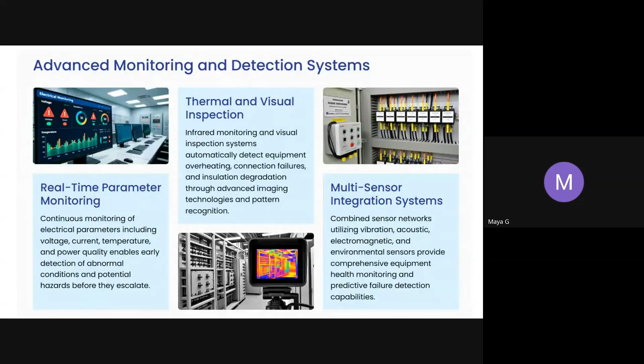So, advanced monitoring and detection systems, I have mentioned a few. Real-time parameter monitoring: continuous monitoring of electrical parameters, including voltage, current, temperature, and power quality, enables early detection of abnormal conditions and potential hazards before they escalate. Thermal and visual inspection: infrared monitoring and visual inspection systems automatically detect equipment overheating, connection failures, and insulation degradation through advanced imaging technologies and pattern recognition. Multi-sensor integration: a combined sensor network utilizing vibration, acoustic, electromagnetic, and environmental sensors provides comprehensive equipment health monitoring and predictive failure detection capabilities.